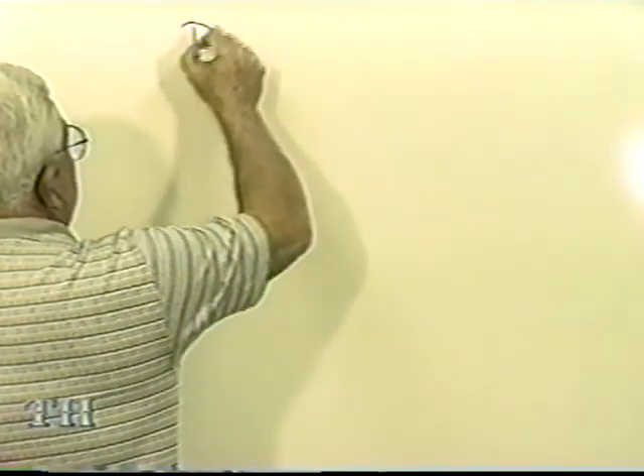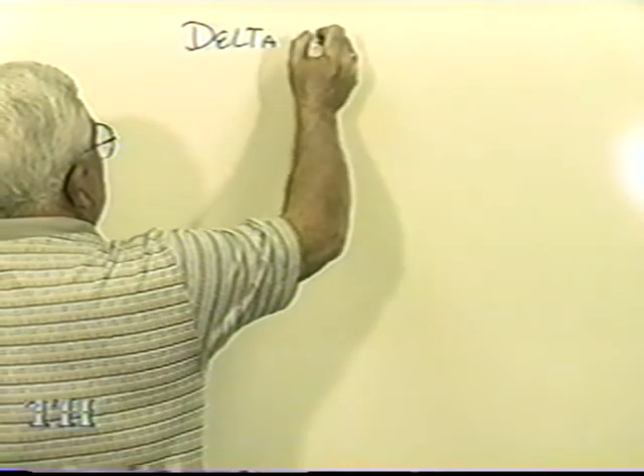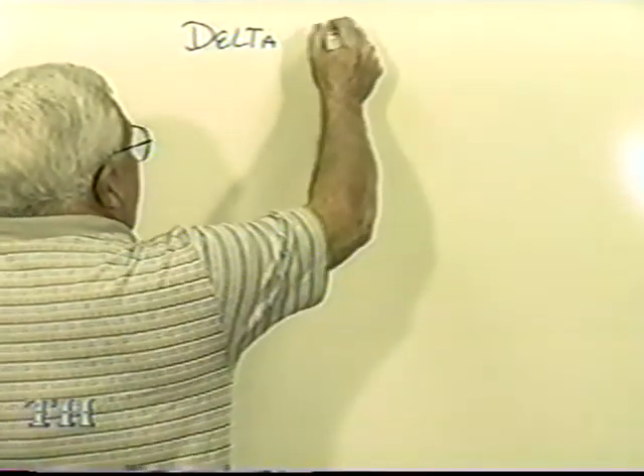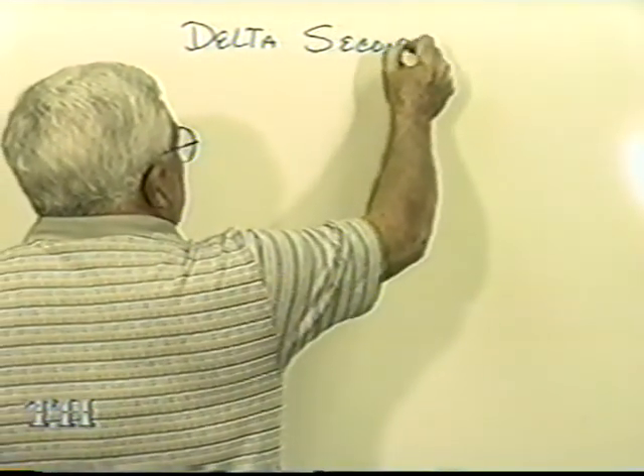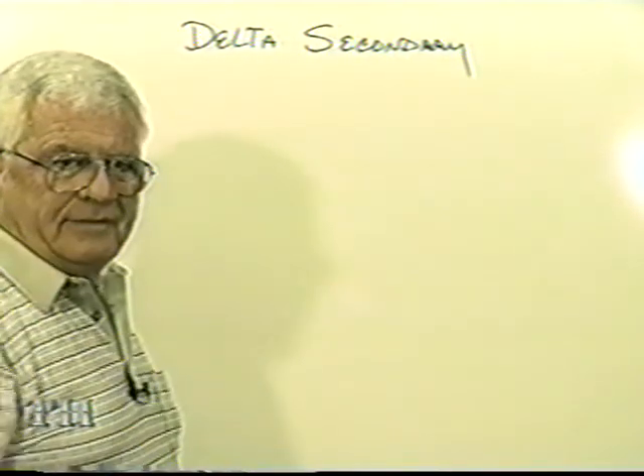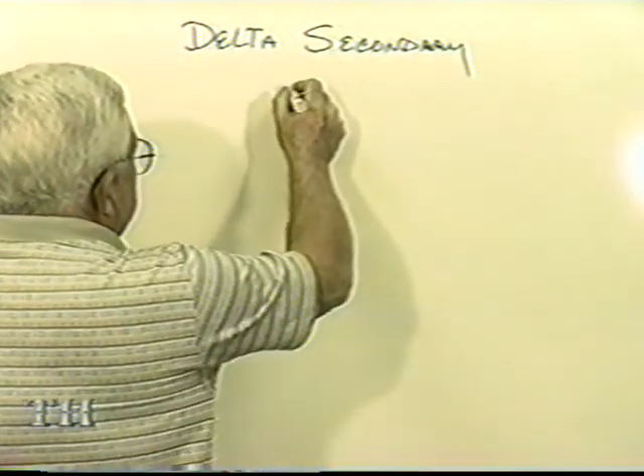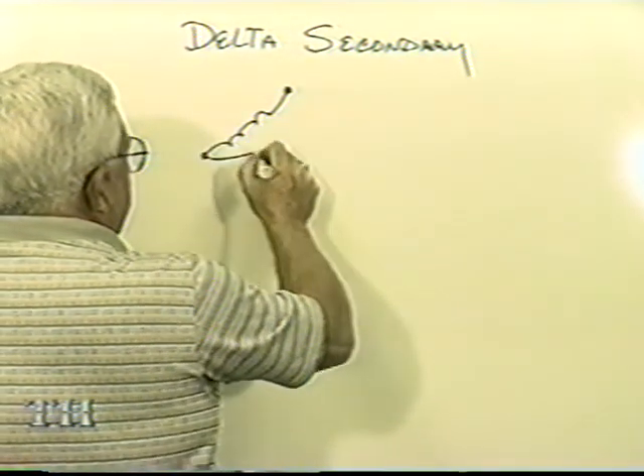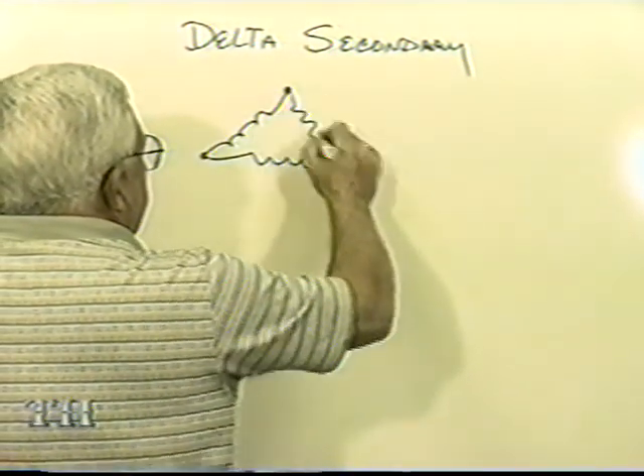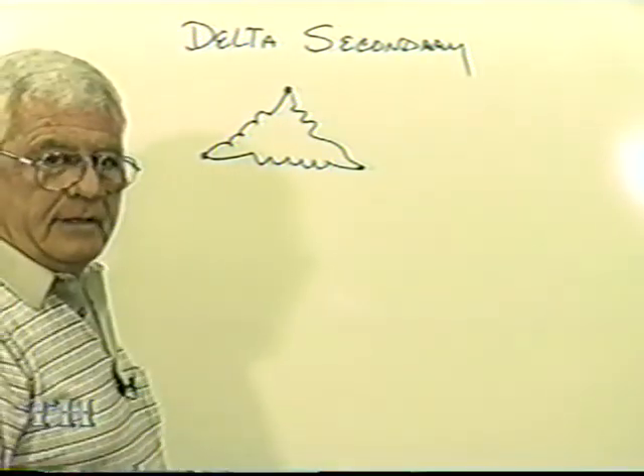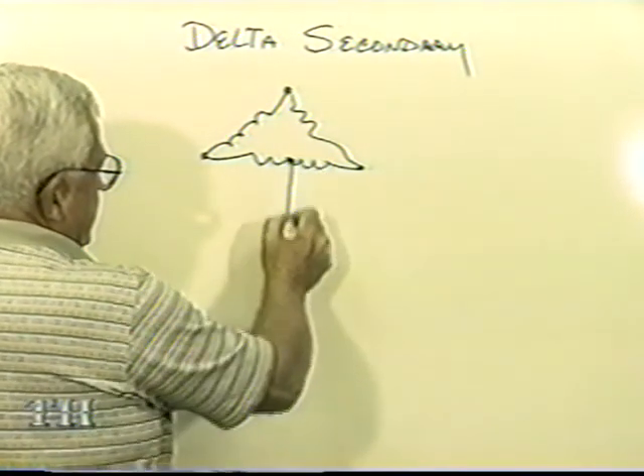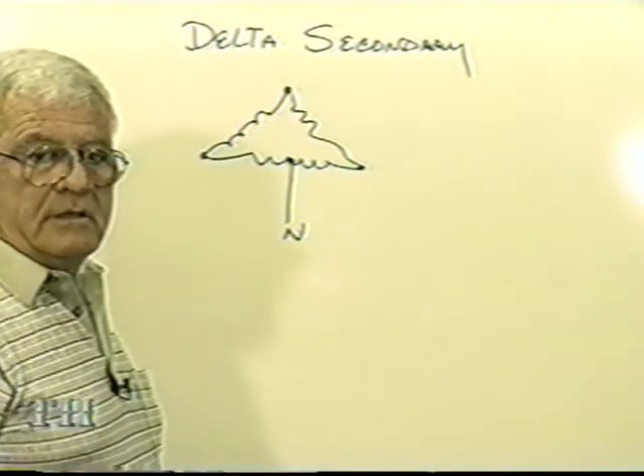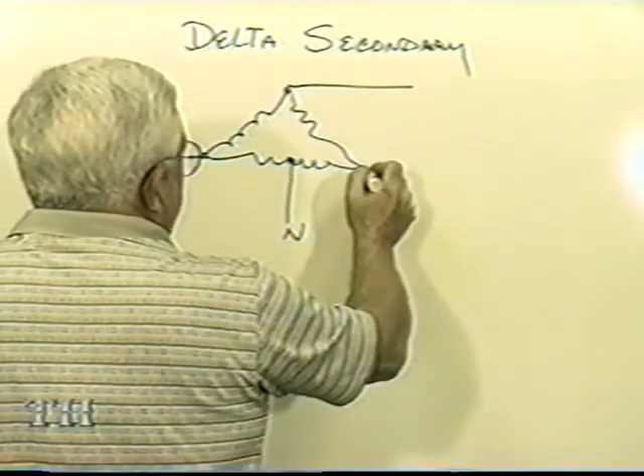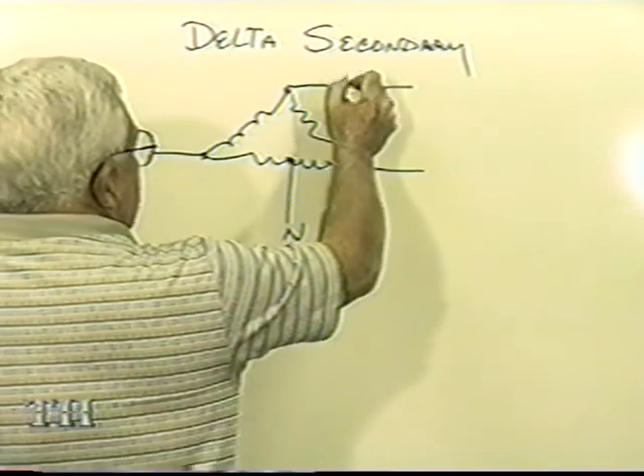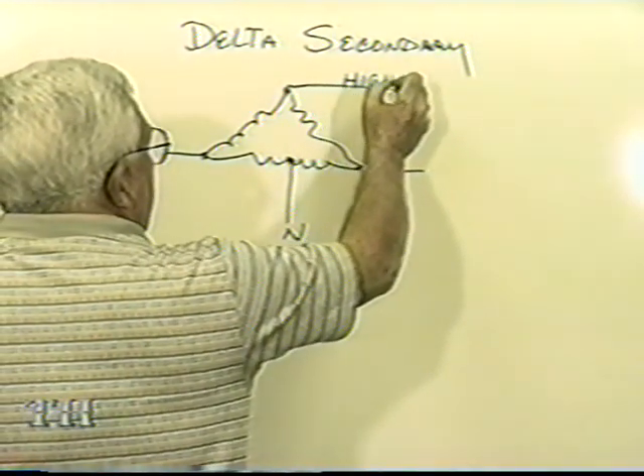Example: say you have a delta secondary. And I mentioned earlier, some places today don't want it, but you have it in areas throughout the United States. Well, here's our delta secondary. Now, when you say secondary, look, it's going to have a neutral. And here comes your wires, your line wires. Well, see up here is what they call the high leg.